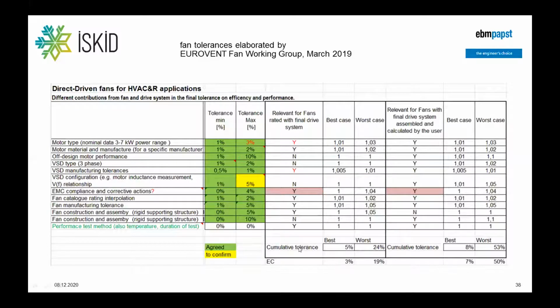So it could be, for AC motors, between 5 and 24%. The EC calculation, so if it's a PM motor or EC motor used, it's between 3 and 19%. And if the final drive is assembled and calculated by the user, the overall tolerance is between 8 and 50%. So this is really a big difference, and therefore really good data are only wire-to-air data.